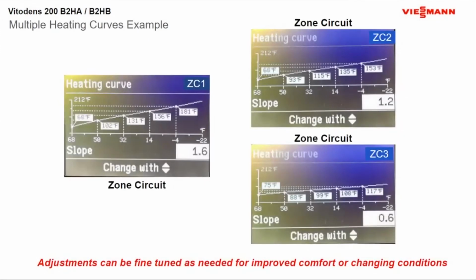This is just showing you how to set multiple heating curves, what they would look like if you set a 1.6 heating curve, or a 1.2 heating curve, or a 0.6 heating curve. You can see the different temperatures while you're looking at the different heating curves. That's what I liked about this boiler here, is that we can see the actual temperatures that we're setting our curves to, and not just setting it to a baseboard type of slope or whatever.